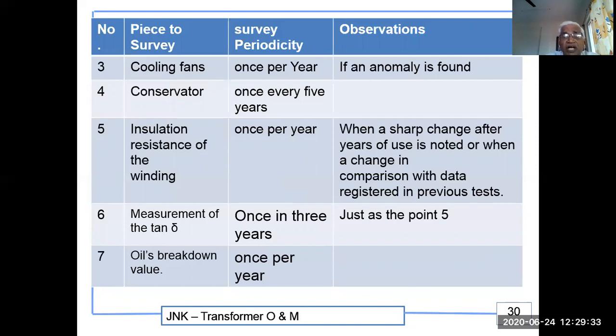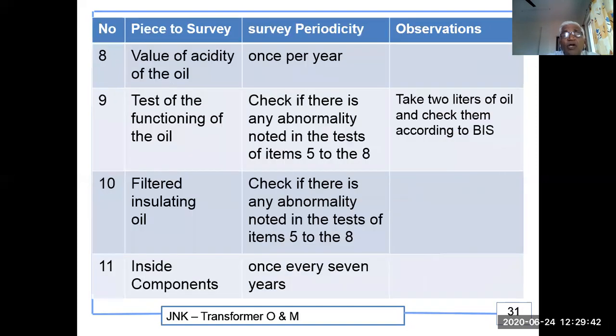Measurement of tan delta, once in 3 years, just as in item 5. Oil breakdown value, once in every year. Value of acidity of the oil, once per year. Test of the functioning of the oil. Check if there is any abnormality noted in the tests of items 5 to 8. Filtered insulating oil. Check if there is any abnormality noted in the tests of items 5 to 8. Inside the components, once in every 7 years, we should do that.